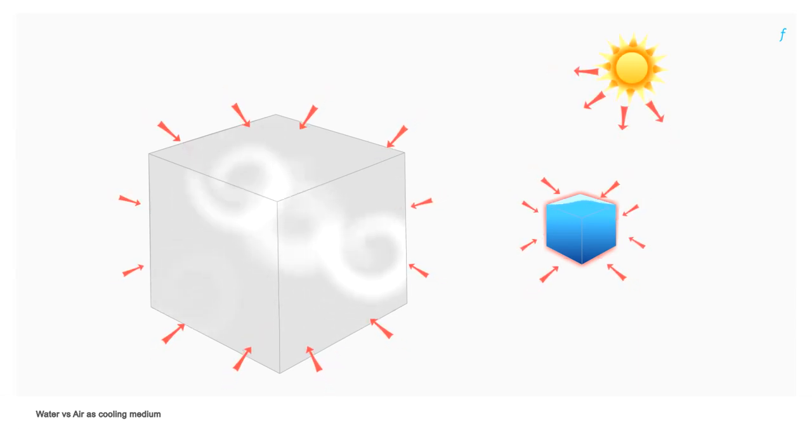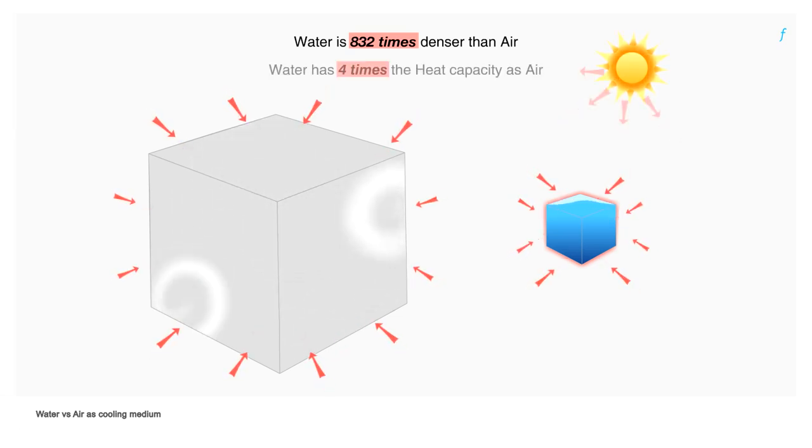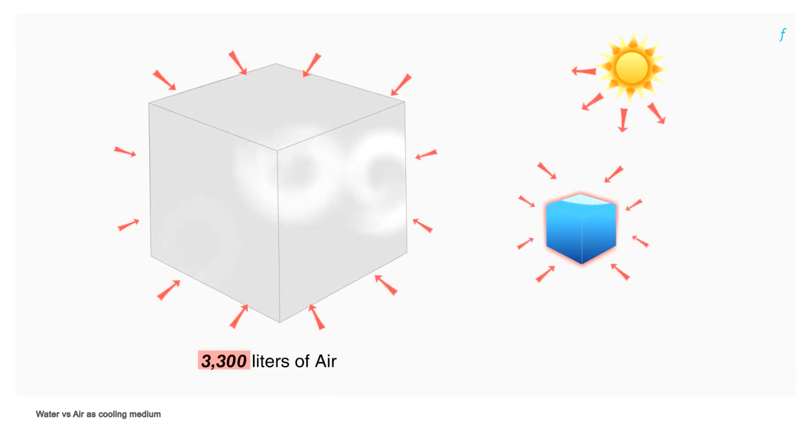Water is 832 times denser than air and has approximately 4 times the heat capacity as air. Effectively, one must circulate 3,300 liters of air as opposed to 1 liter of water to absorb the same amount of heat.